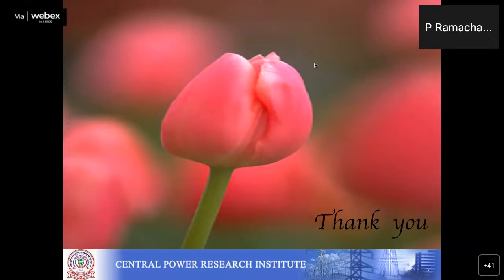So during this period, I believe in KSEBEA, this may be maximum in hydroelectric stations, especially old hydroelectric stations, where small auxiliary transformers were used inside the power station, near the generator or turbine. Probably those may have this non-inflammable PCB. So such transformers, especially if made before '85, an imported transformer, better to carefully check it. Unfortunately it may not even be on the nameplate, but sometimes they put a special rating plate stating that it contains PCB.